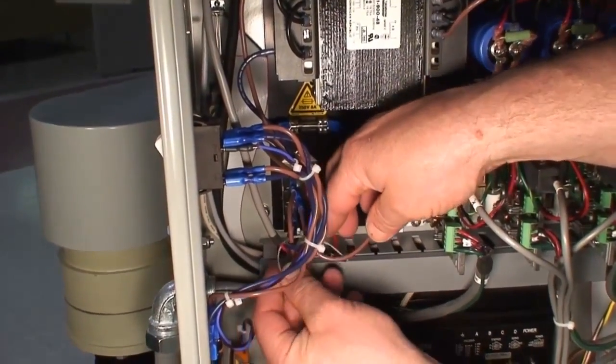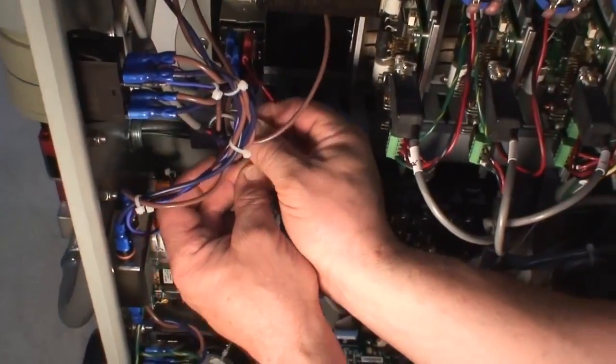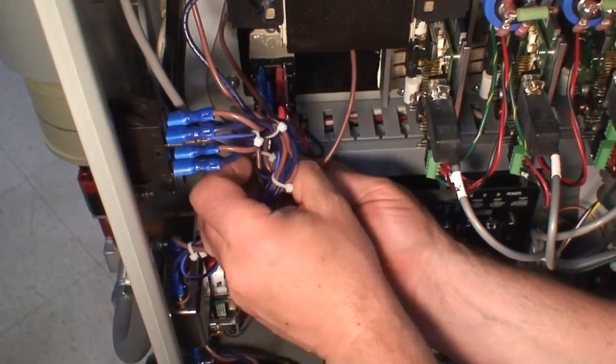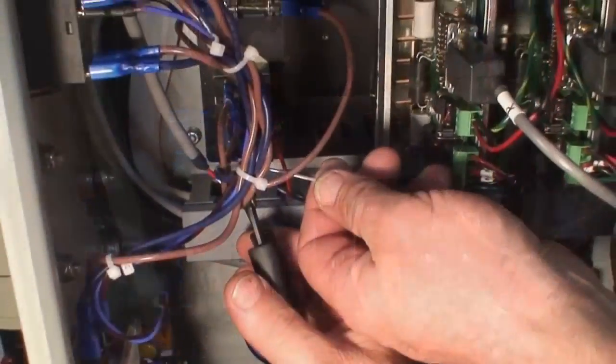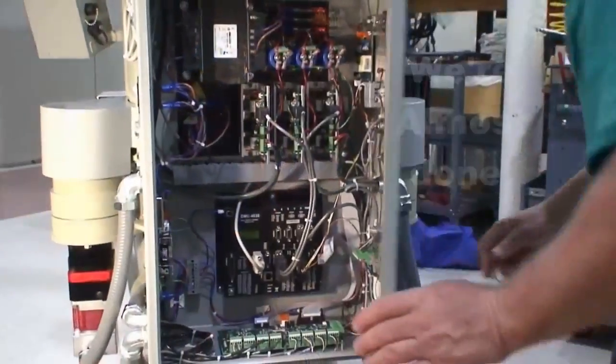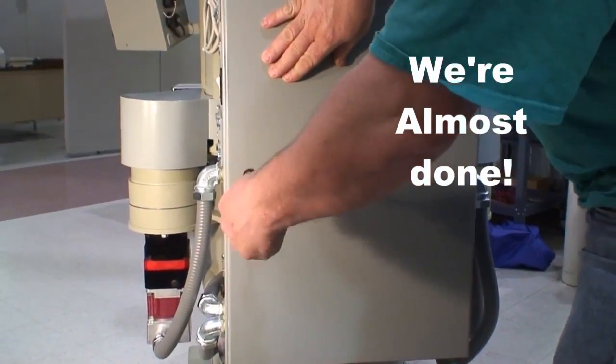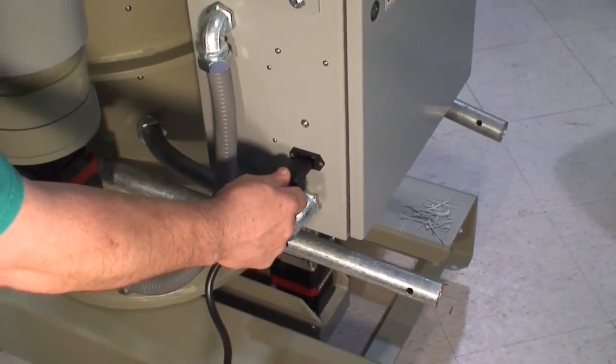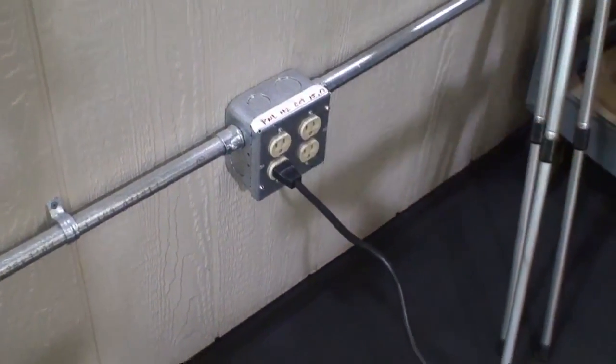Now bundle these wires back together. Put the new wires in the bundle also. Make sure you've removed all your tools and nuts and bolts and everything from the cabinet. Close the door and latch it. Plug the power cord back into the G2 and plug it into the wall outlet. Turn the power switch on.